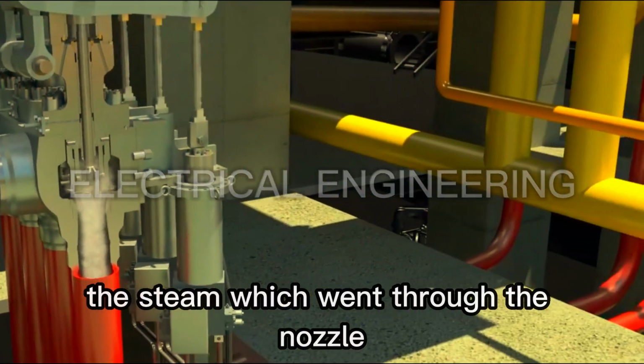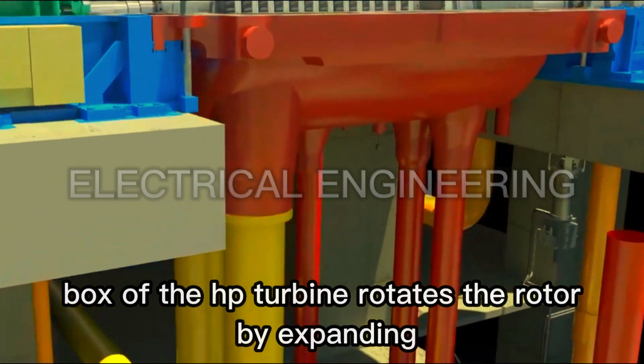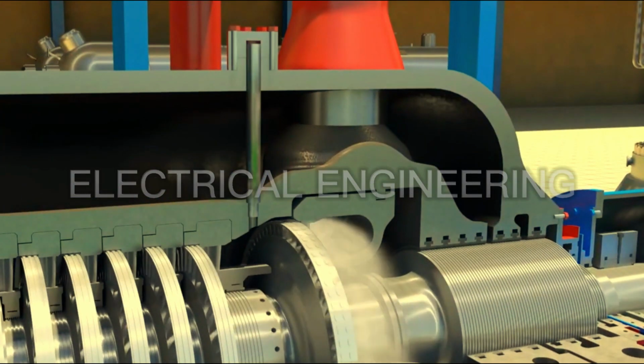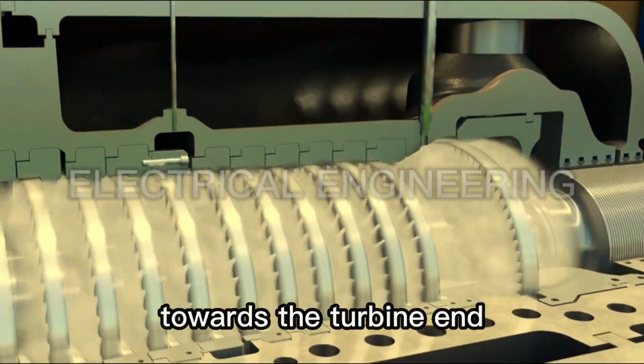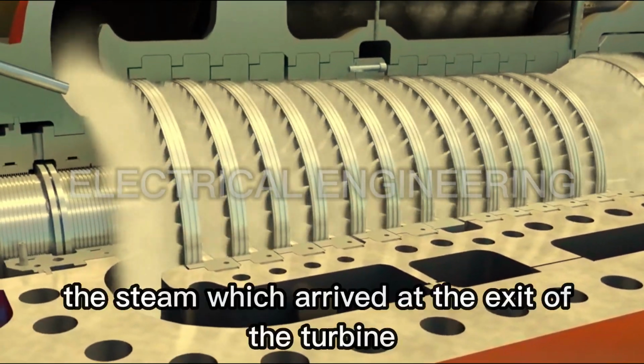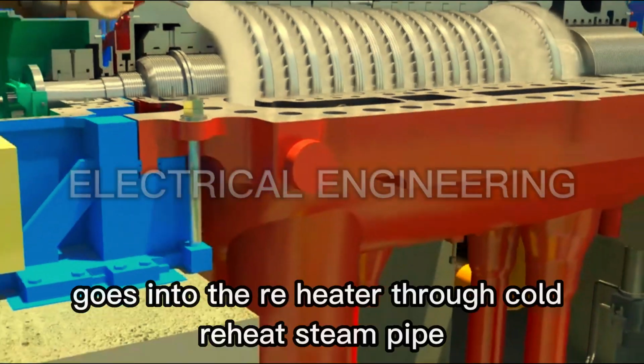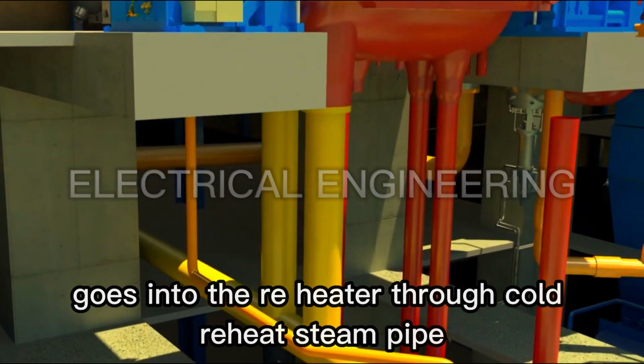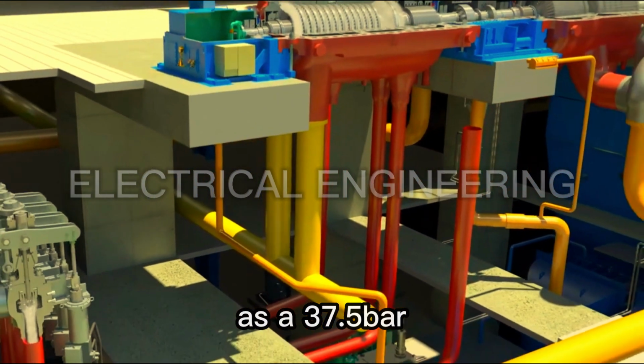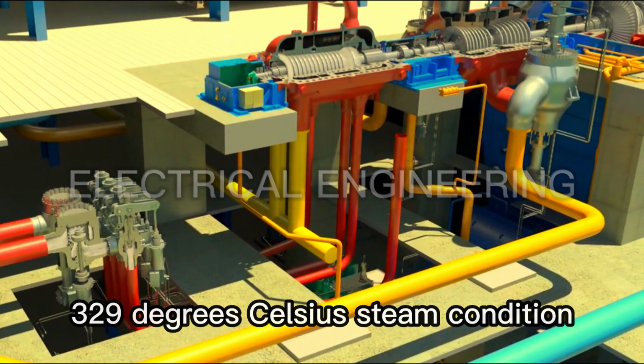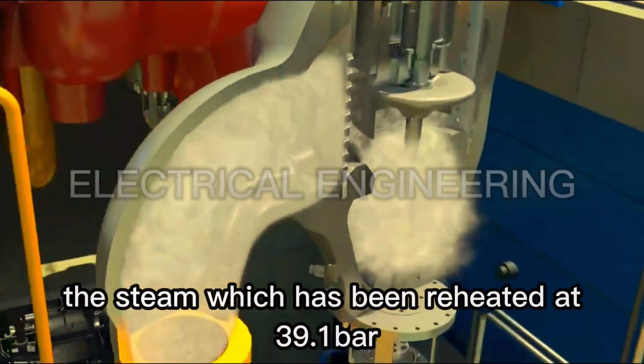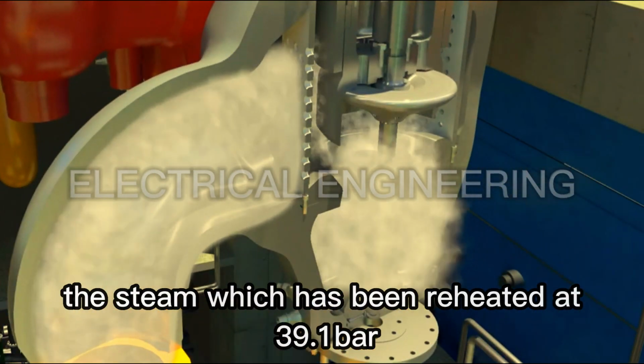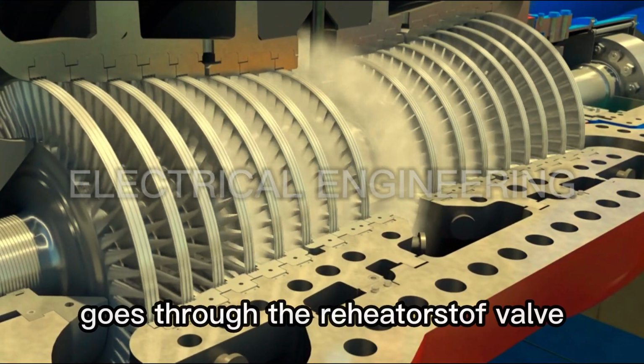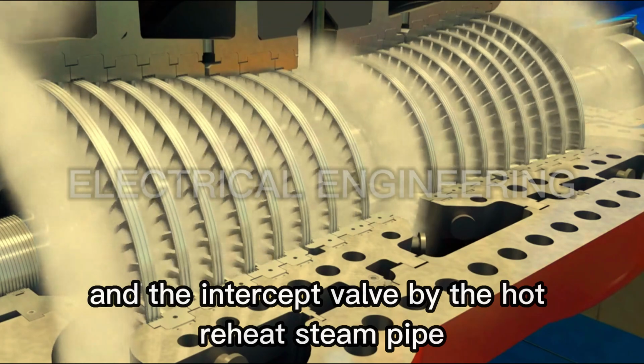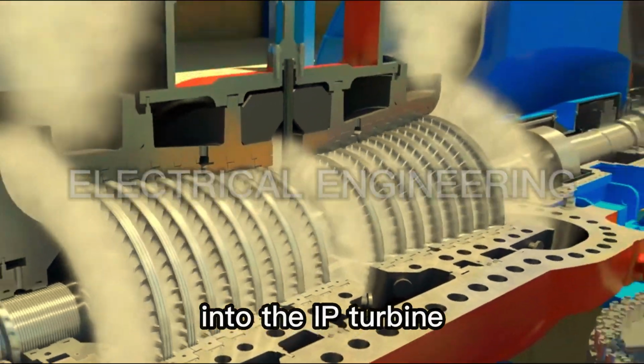The steam which went through the nozzle of the HP turbine rotates the rotor by expanding, after going through 14 impulse stages towards the turbine end. The steam which arrived at the exit of the turbine goes into the reheater through cold reheat steam pipe as a 37.5 bar, 329 degrees Celsius steam condition. The steam which has been reheated at 39.1 bar, 541 degrees Celsius in the reheater goes through the reheater stop valve and the intercept valve by the hot reheat steam pipe into the IP turbine.